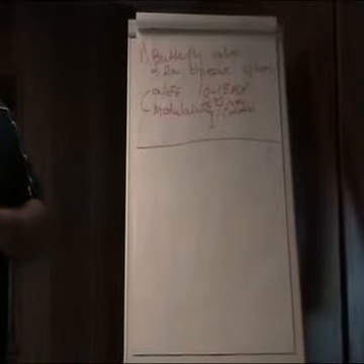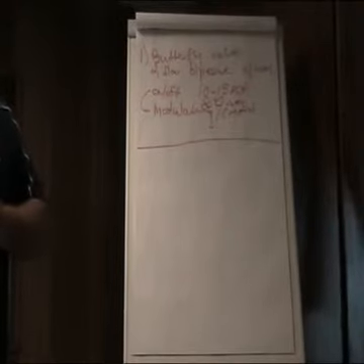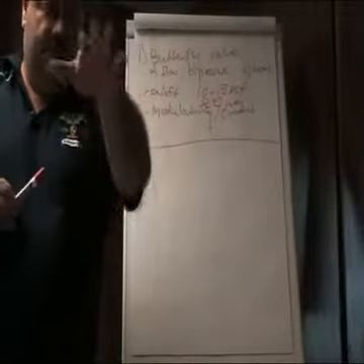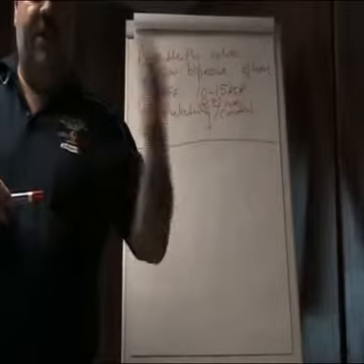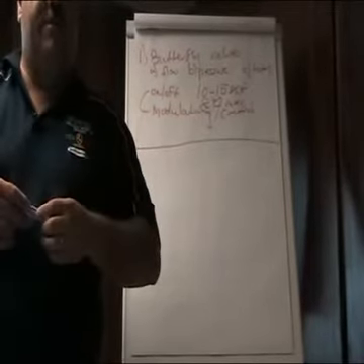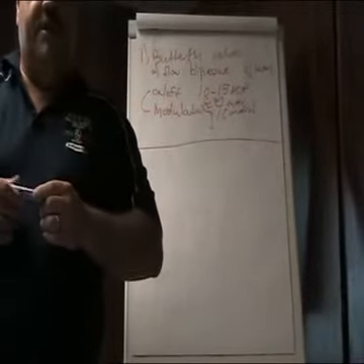What is the biggest minus degrees you can take? No, I'm not sure on the minus. But usually, when you get cryogenic, remember cryogenic, good question, anything minus 100 degrees is called cryogenic. Yeah. You cannot do that with soft rubber lined butterflies. You have to go to a high performance disc valve. That's where the Monel and those special materials come in.